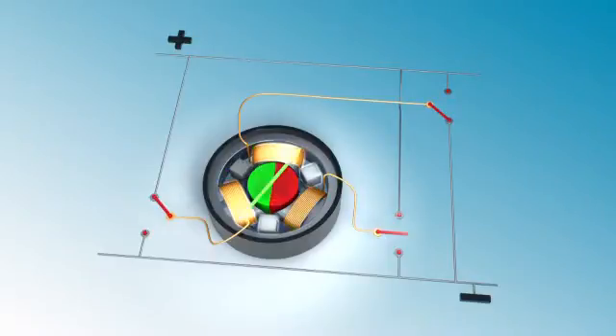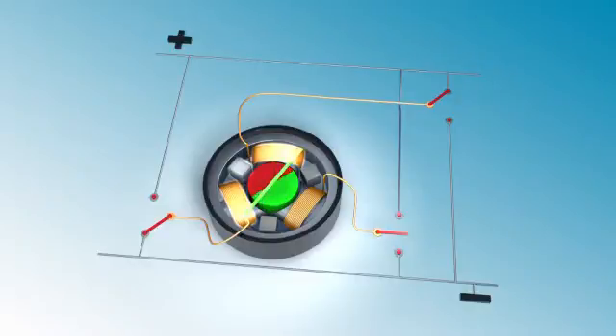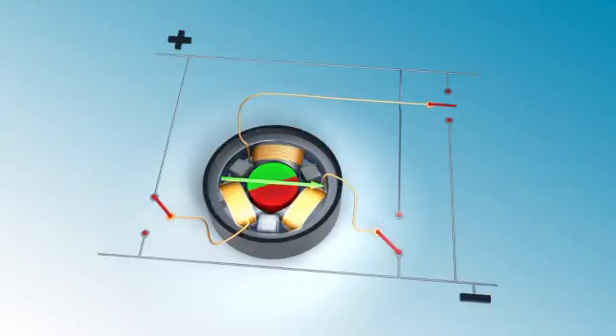In order to make the motor rotate, the stator coils must be switched on and off in a certain sequence that generates a rotating field. This is also known as trapezoidal or block commutation. Now the rotor follows this rotating stator field.